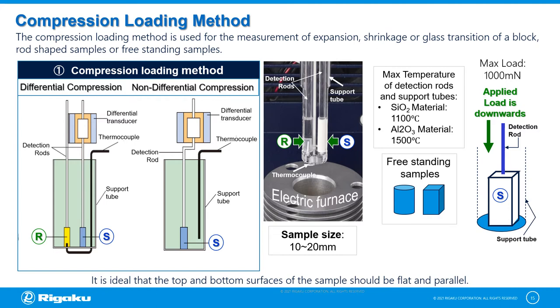Rigaku provides the differential type and non-differential type compression loading attachment. The maximum load that can be applied is 1000 mN. The maximum operating temperature depends on the detection rod and support pipe. For measurements up to 1100 degrees centigrade, we use the quartz type detection rod and support pipe. For measurements up to 1500 degrees centigrade, we use the alumina type detection rod and support pipe.